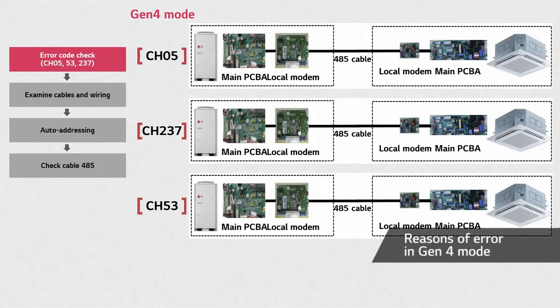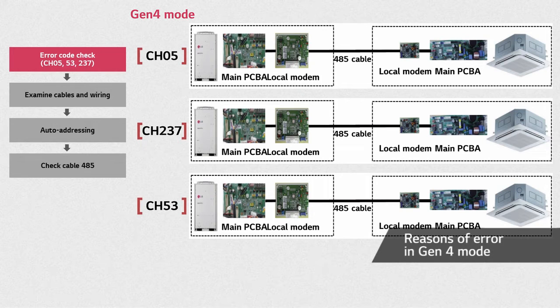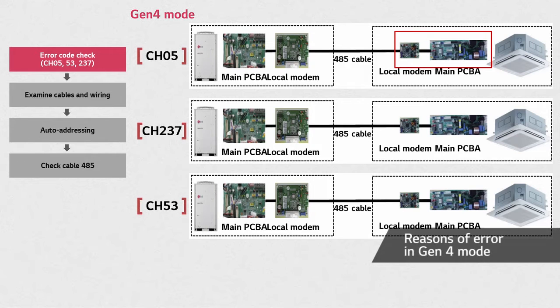As already mentioned, CH05, 237, and 53 are communication errors. When the IDU and ODU are set in Gen4 mode, CH05 indicates an error between the local modem and the main PCB of the indoor unit.